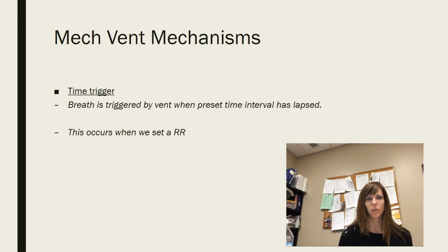So whenever you're setting the respiratory rate by turning that knob to 12, in essence, you're telling the computer to calculate the IE ratio and the inspiratory time, and the expiratory time is what's left over, by which the respiratory rate should be 12. I know that sounds confusing, but it'll make more sense on the next slide.